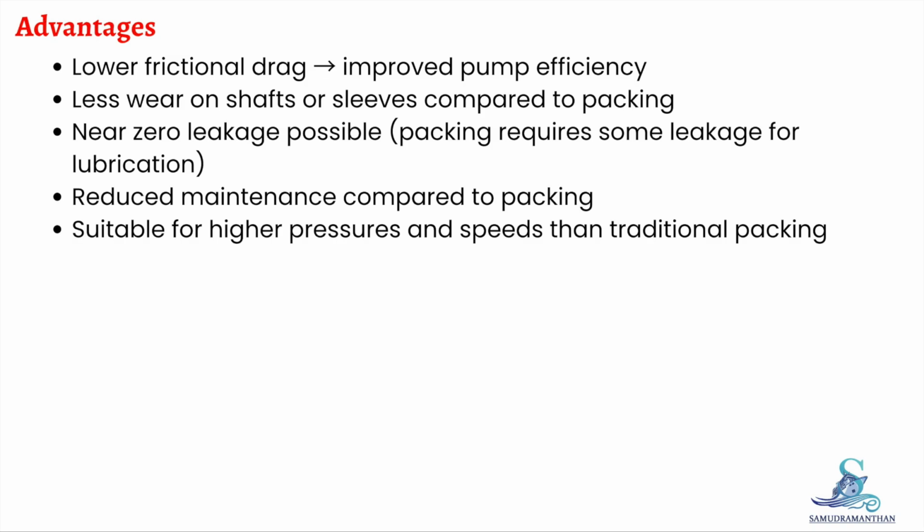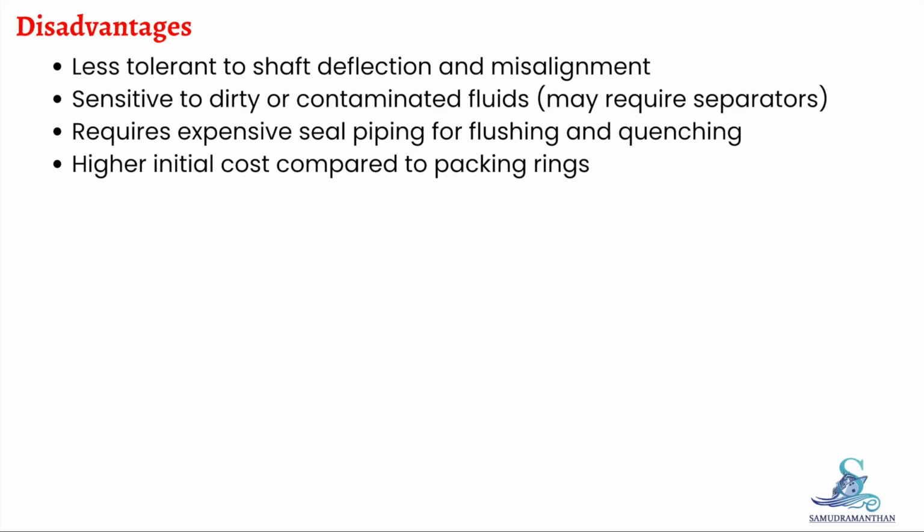Disadvantages: less tolerant to shaft deflection and misalignment, sensitive to dirty or contaminated fluids, may require separators, requires expensive seal piping for flushing and quenching, higher initial cost compared to packing rings.